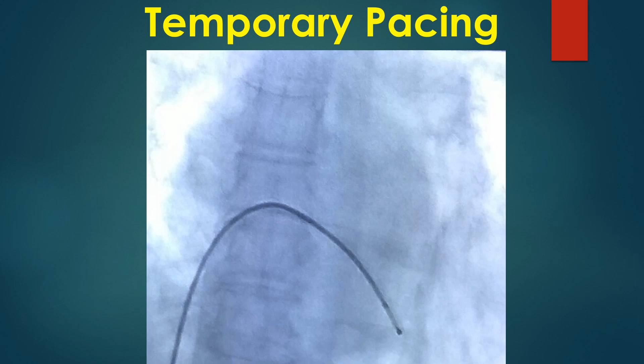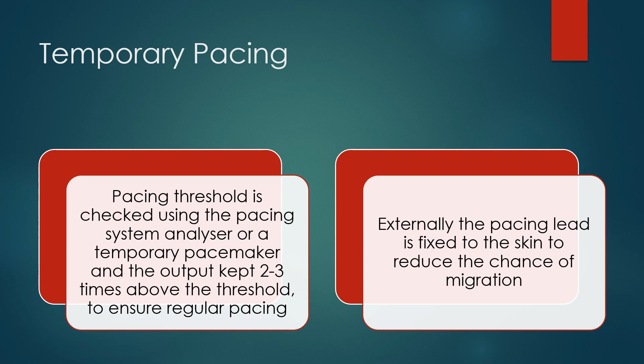Pacing threshold is checked using the pacing system analyzer or a temporary pacemaker and the output kept 2 to 3 times above the threshold to ensure regular pacing. Externally, the pacing lead is fixed to the skin to reduce the chance of migration. Temporary transvenous pacing can also be done from the jugular, transjugular pacing, or subclavian routes by percutaneous puncture.